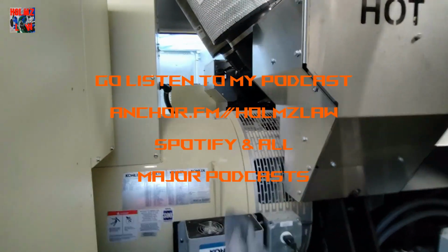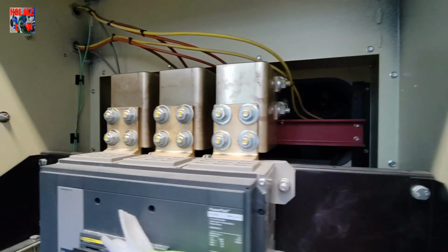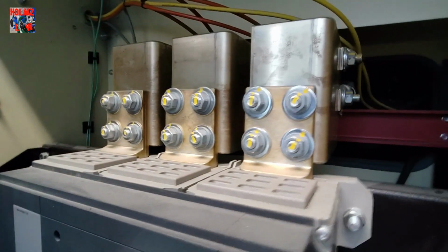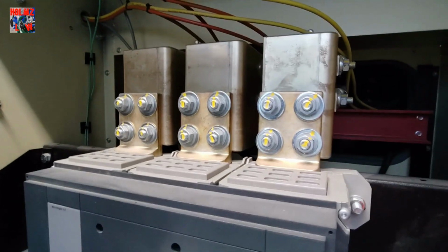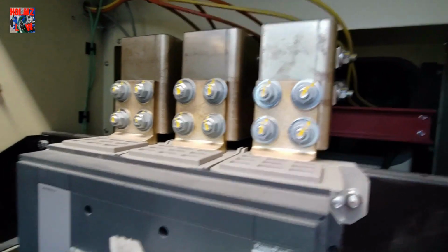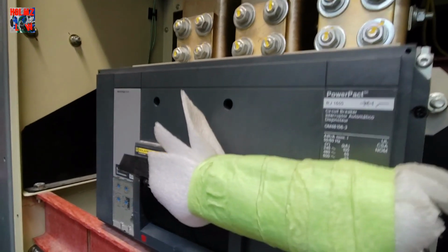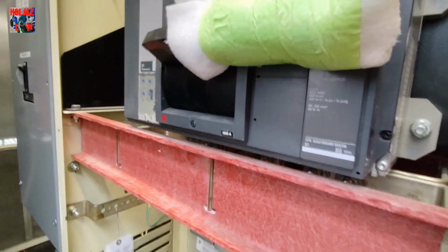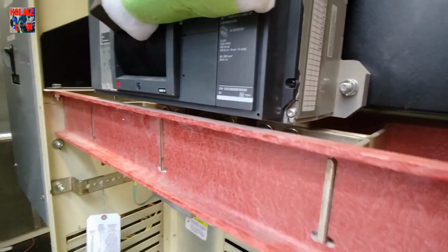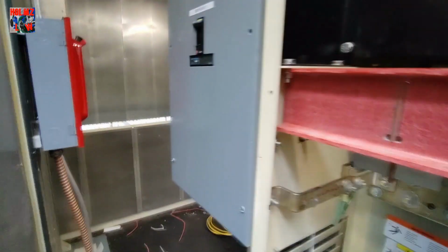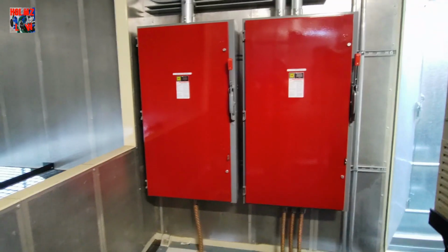And more importantly than anything, it needs to be a four-pole transfer switch so that you can also switch the neutral as well as the phases. So in a bit, I'm going to show you that transfer switch. For now, let me just show you a little bit around the actual generator enclosure.